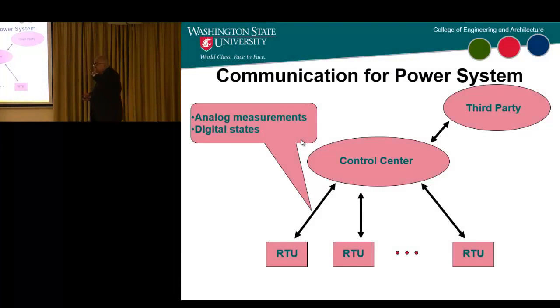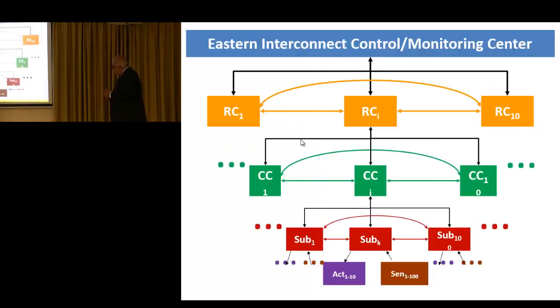Okay, so now if I think of a control center, the way it used to work—well, it still does—is that we have these remote terminal units in each substation, and they have communications to the first level control center, where your SCADA AGC is, and then above this would be the reliability coordinator. I'll skip this.